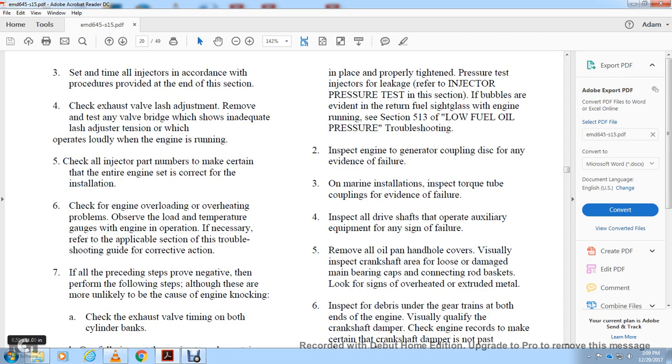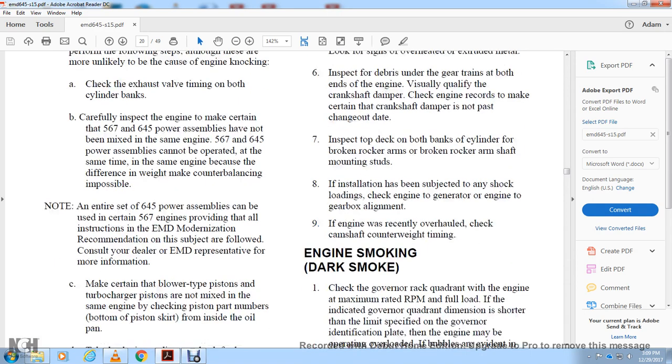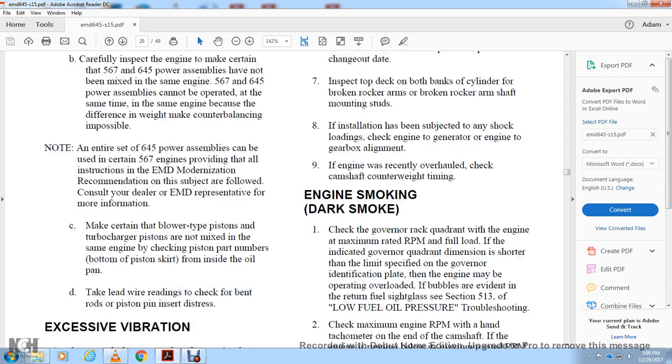Check for engine overloading and overheating. Refer to the applicable troubleshooting section for corrective action. If all preceding steps prove negative, perform the following steps. Although unlikely, check the exhaust valve timing on both cylinder banks. Carefully inspect the engine and make certain that 567 and 645 power assemblies have not been mixed in the same engine — they cannot be operated together due to differences in weight and counterbalance. An entire set of 645 cubic power assemblies can be used in certain 567 engines provided all Electro-Motive Division conversion recommendations are followed.